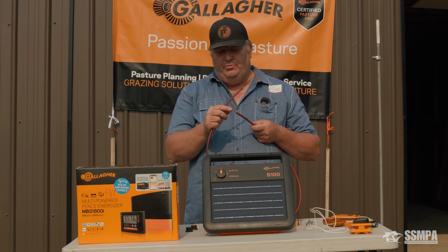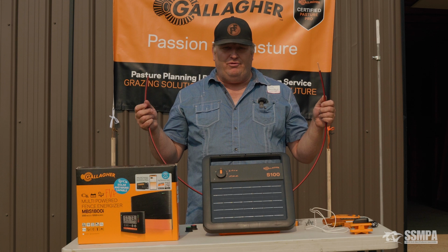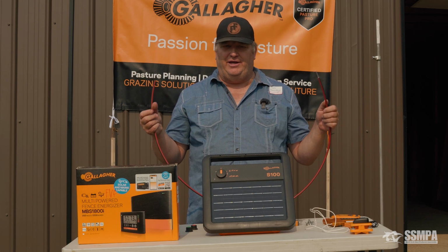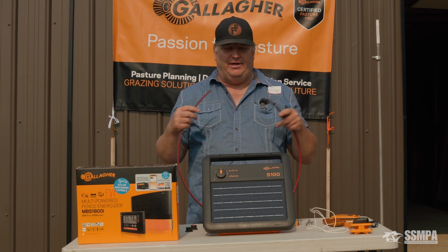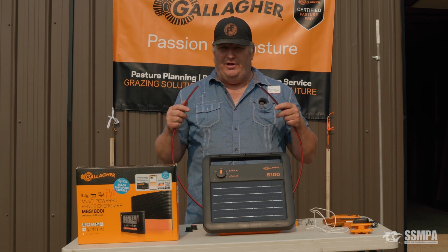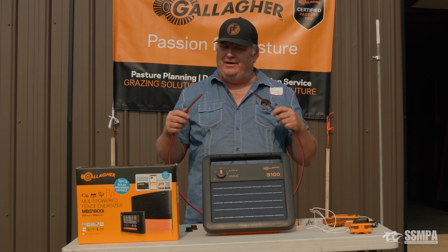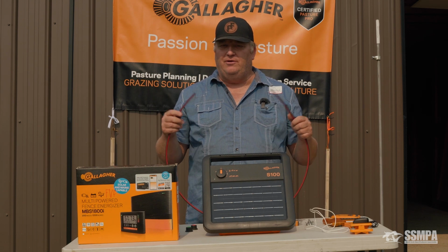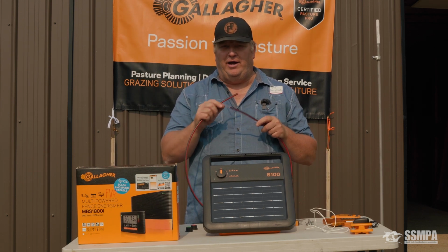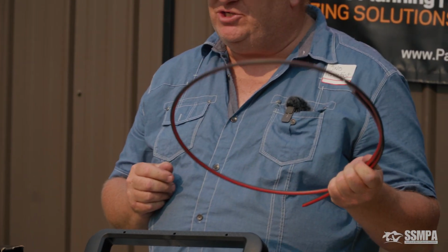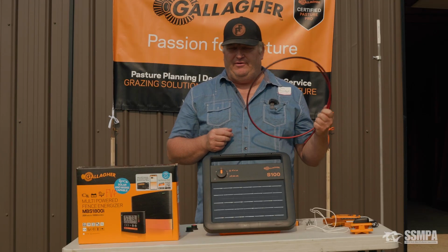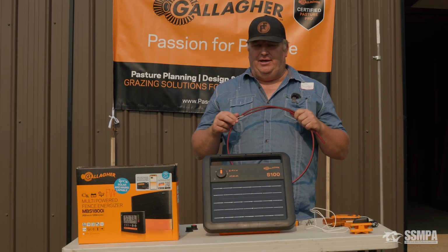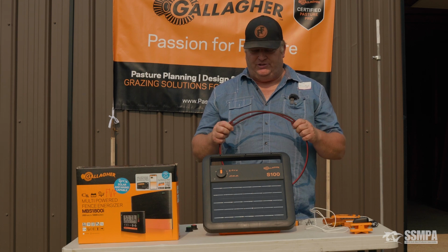So with the aluminum, I can pass the equivalent of 3 wires under my gates or lead out to the fence, whatever it is. I use this on energizers 8 joules and greater. Under that, I generally just use the heavy duty lead out cable from Gallagher, which is a black cable and just straight wire. It doesn't have the aluminum coating. It's important to use this so you don't have any leakage on your fences or stray voltage, say going out through a building. And again, if I'm going underground, I want to make sure this is shielded well. Lots of times, even in a building or underground, I'll put it in an additional conduit for extra protection as well.